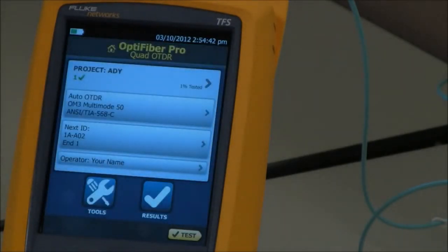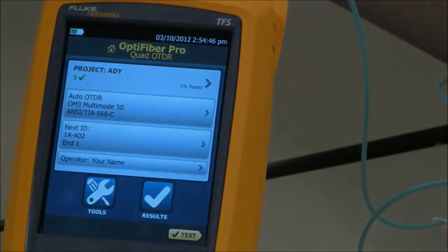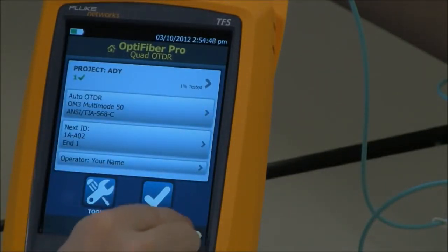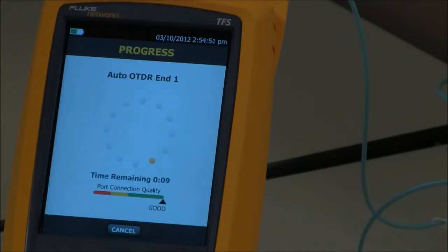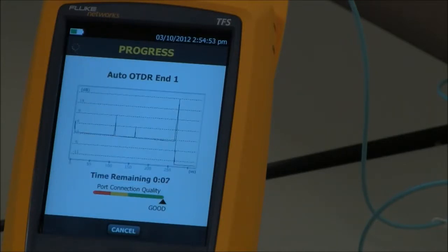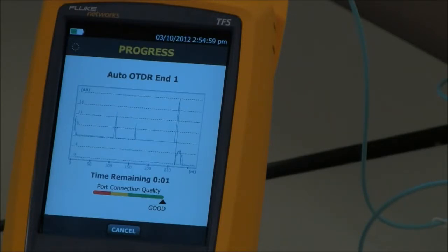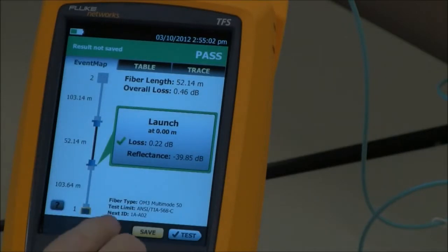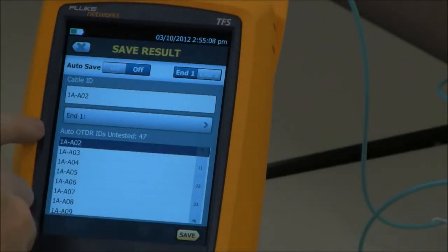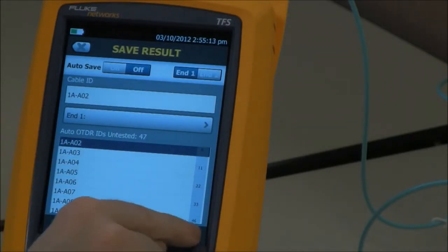If I touch the home screen now, I've got 1 test and it says 1% is tested. Let's run another test. For a multimode link, expect about 12 seconds for an auto test unless there's something wrong with the link. My next ID is A02 — that's what it's going to save as, so save. I can't select A01 now because it's been done already; it's jumping to A02.